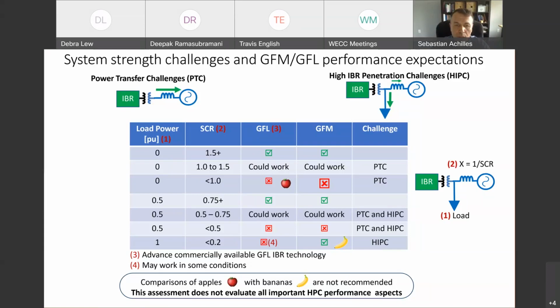Now, it's a comment about the apple and the banana. It's very common in the industry to talk about grid following operating for short circuit ratios of 1 or 1.5 and above. Grid forming can operate to a short circuit ratio of 0. So one is an apple, the other one is a banana. It is true that grid forming can operate with short circuit ratio close to 0, provided there is no power transfer limitation that prevents you from doing so. So if grid forming has a power transfer limitation, it will probably be constrained also for short circuit ratios close to 1, similarly to the way grid following is constrained.